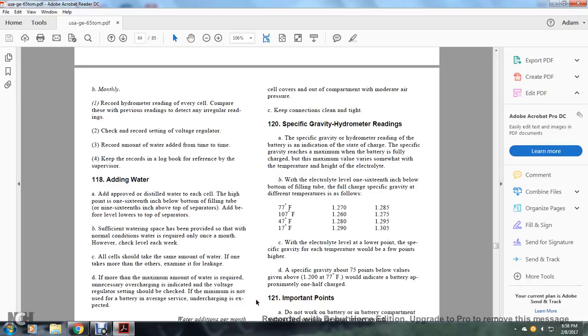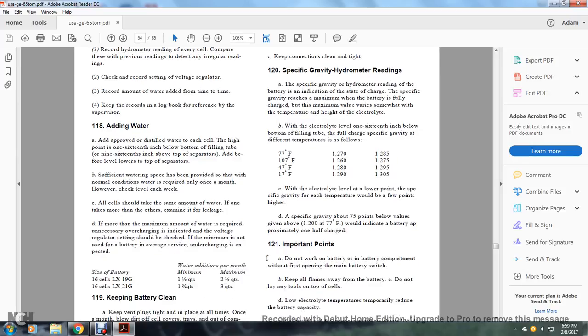the full charge specific gravity at different temperatures is as follows: 77 degrees Fahrenheit, 1.270 to 1.285; 47 degrees Fahrenheit, 1.280 to 1.295; 17 degrees Fahrenheit, 1.290 to 1.305. With electrolyte level lower, specific gravity for the same temperature would be a few points higher. Specific gravity about 75 points below the values given, around 1.200 at 77 degrees Fahrenheit, would indicate the battery is approximately half charged.